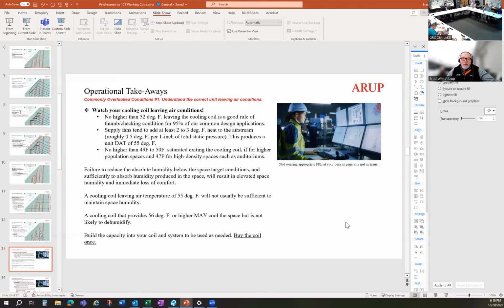The first thing I look for is, was the coil designed to get the air significantly below the dew point of the air, so that it has room to absorb the moisture that's generated within the space, or comes in with ventilation, or comes in from any source? Be it a swimming pool, open tanks, or just a lot of people breathing. It's a lot of moisture to deal with.